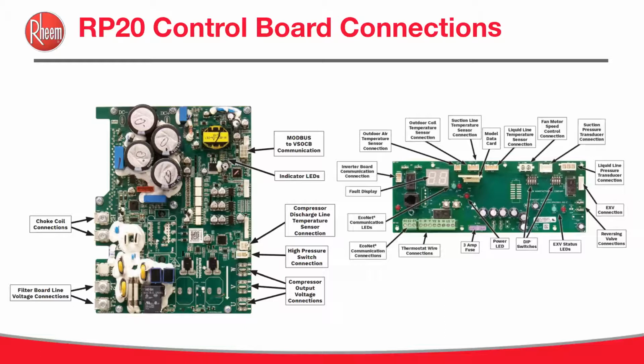Having a dual 7-segment LED reduces the time and the possibility of misinterpreting fault codes with flashing LED lights alone. There are, however, LEDs to show if the power is present. So as you can see here, power LED, there is a red light, so that at least you know that you have power there if you don't have the multimeter on you at that point.